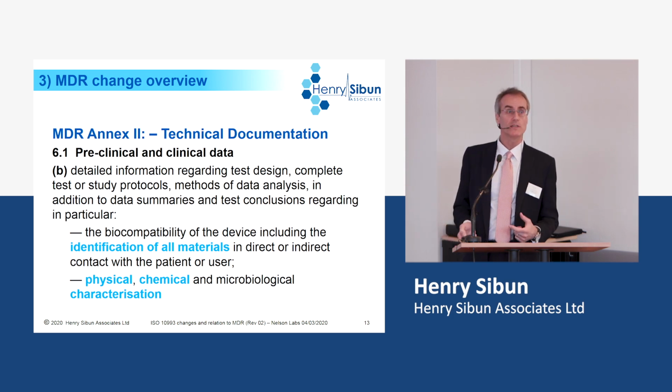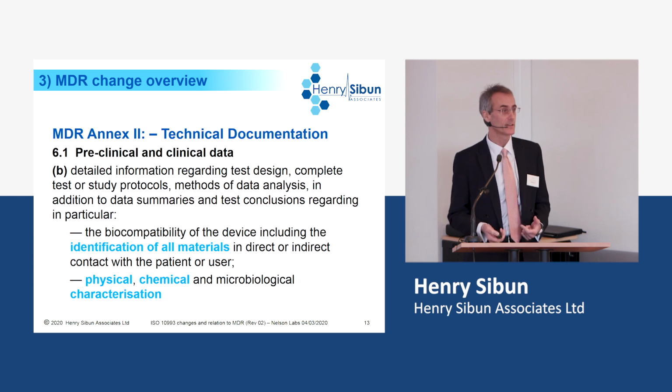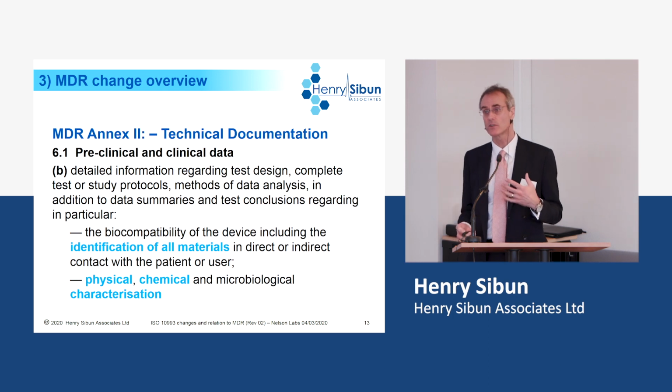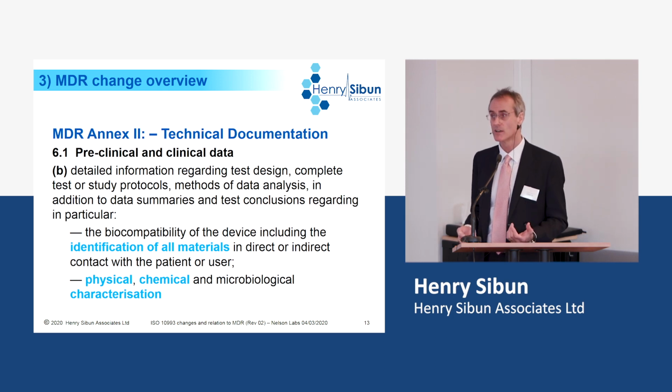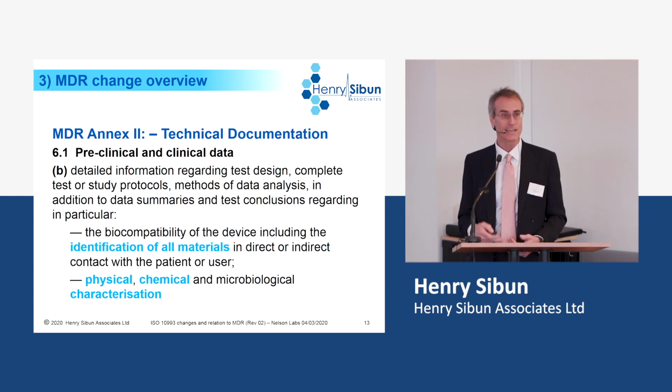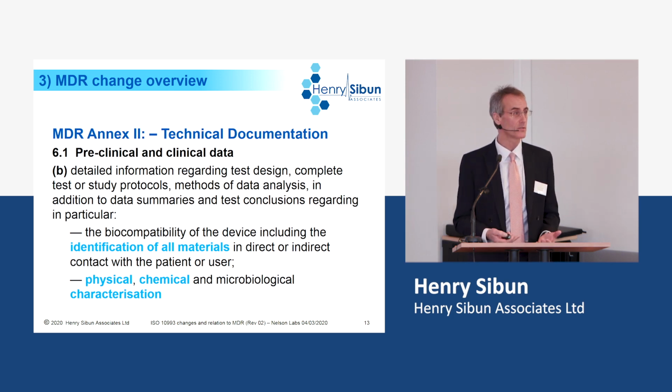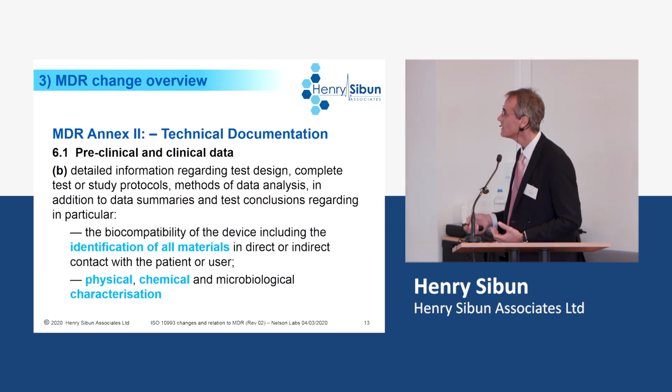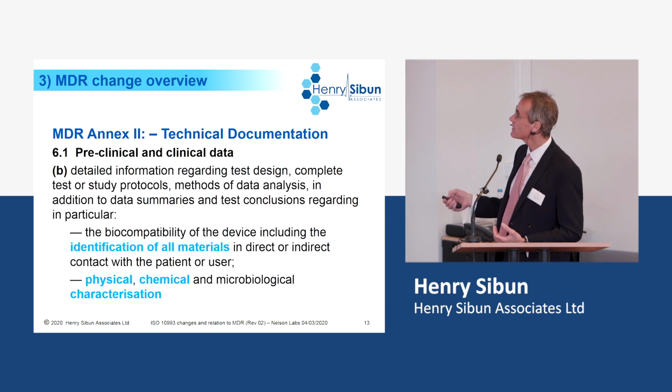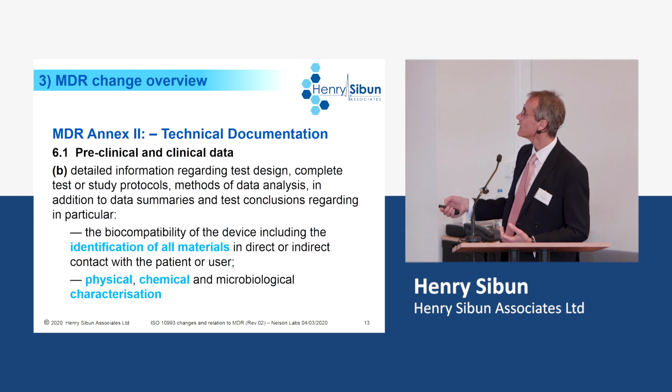That is very commonly missing from a notified body perspective. Okay, companies have the test report, but not the protocols. And typically it's because the protocols have followed pharmacopoeial monographs, but that's not sufficient for medical devices. You need to summarize the test method, in particular, the preparation of the product samples. How are the samples prepared, ready for testing? So you need to have the test design information, protocols, how you analyze the data, and the data summaries of the results and the conclusions. So that must be documented for all of these.